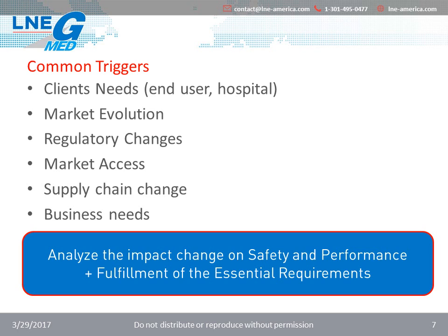It is important to note that minor changes to one device can be considered significant changes to another. This depends on the device risk, the intended use, and other factors involved. For example, a change in color can be purely cosmetic for one device, but can impact the ability to address warnings on another device, which is considered substantial.